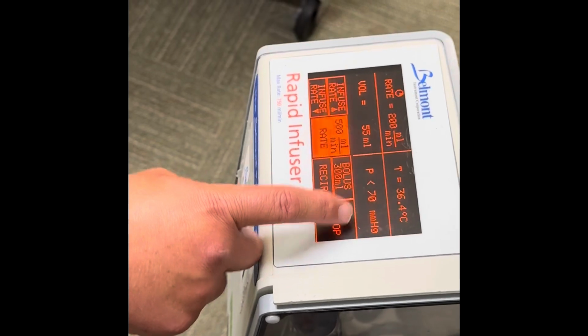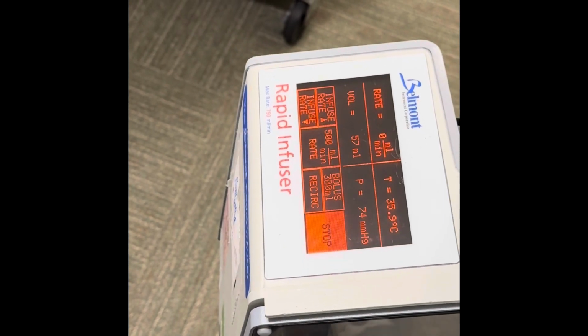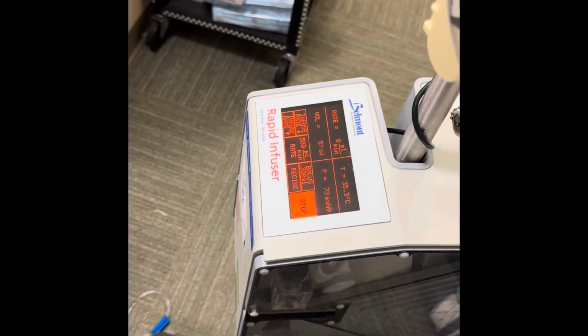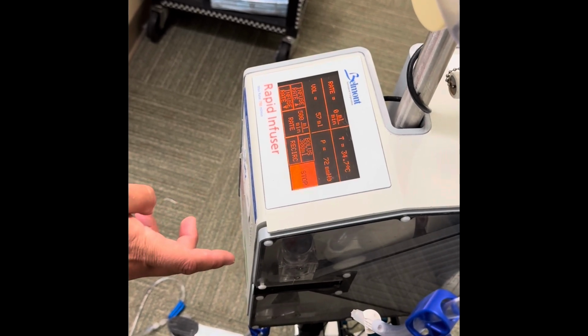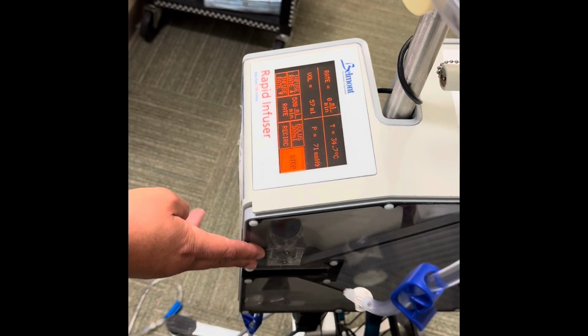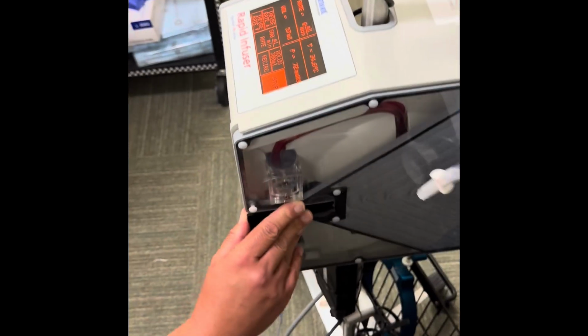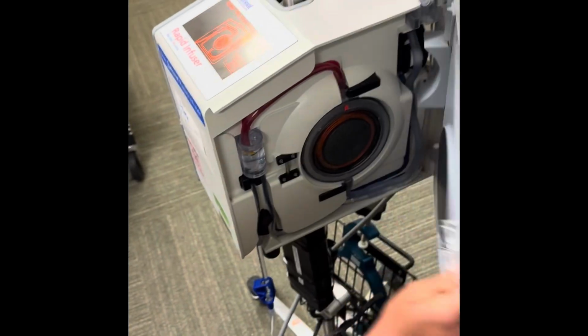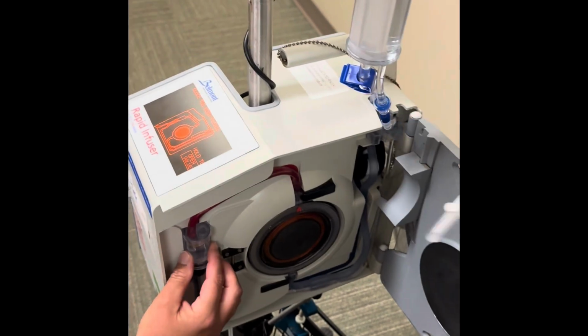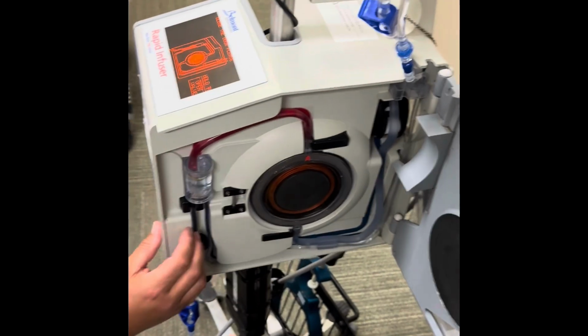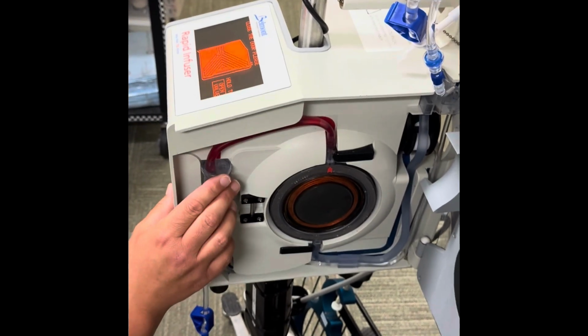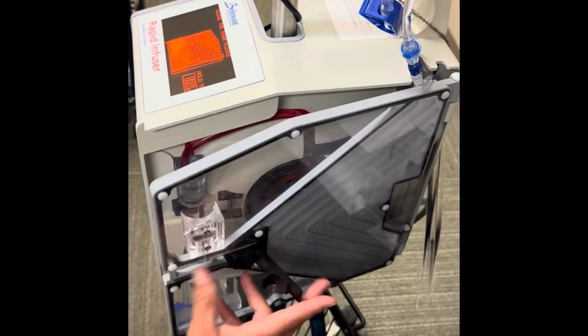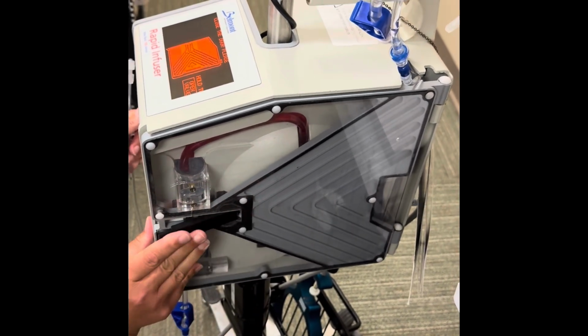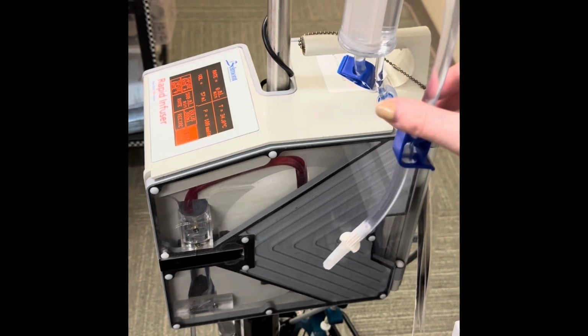Let's talk about what happens if you get a high pressure or high air alert. Be mindful that we can open the chamber door. When you get an air alarm, check this bubbler and give it a squeeze. I always check and squeeze the tubing underneath it. Then close the door and try again at the rate the provider wants us to administer.